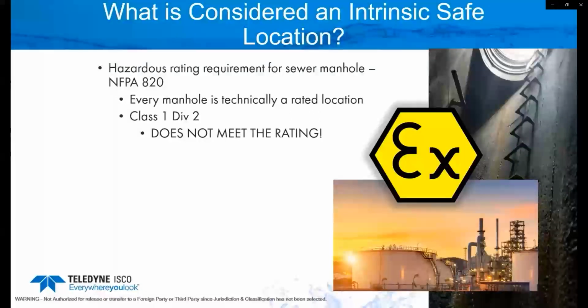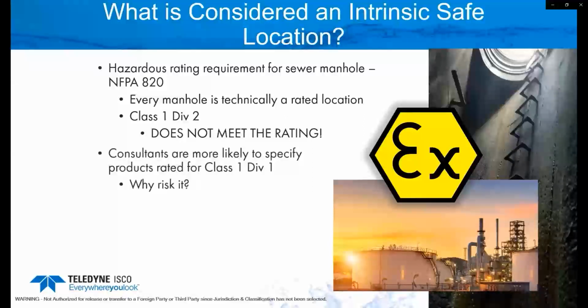So what would be classified as an intrinsic safe location? A hazardous rating for any sewer manhole falls under the NFPA 820 guidelines, and technically every manhole is rated as a Class I Division I manhole. I'll go through this in more detail, but Class I Division II does not meet that rating — another thing to keep in mind. Just because something is kind of intrinsic safe doesn't necessarily mean it meets that rating and falls under the guidelines.